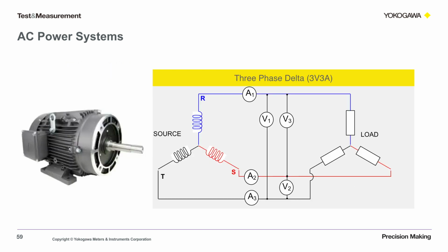A three-phase circuit is commonly used to power large motors and other heavy loads. This specific configuration is a three-phase delta configuration, 3V3A. Three-phase circuits are more economical than an equivalent two-wire single-phase circuit at the same line-to-ground voltage because it uses less conductor material to transmit a given amount of electrical power. In this wiring diagram, there's no neutral, so voltage measurements are made between lines or phases, so the resulting voltage measurement is called line-to-line.